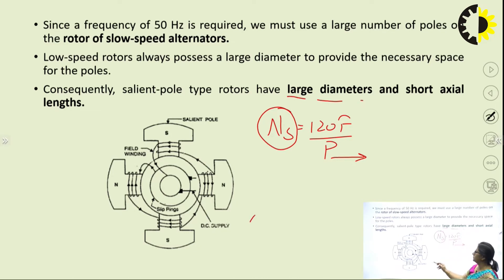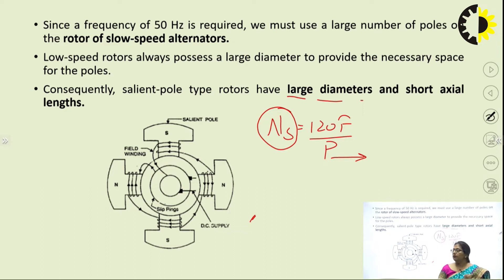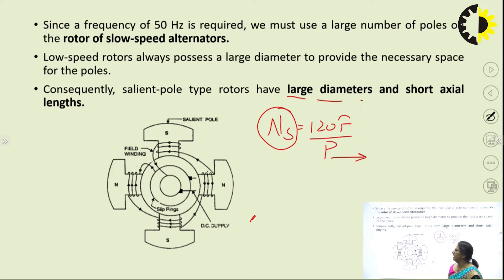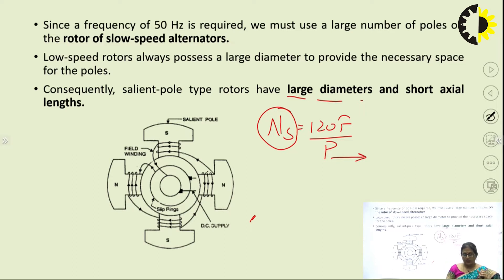For a 50 Hz frequency requirement, slow-speed alternators need a large number of poles. Using NS = 120F/P, more poles require larger diameter. So salient pole rotors are characterized by a larger diameter and shorter axial length. In the figure, the poles project outwards with field windings wound on them, and the larger diameter accommodates more poles for lower speeds.